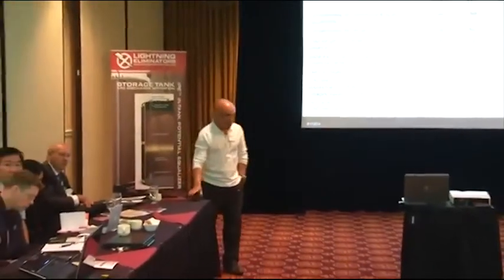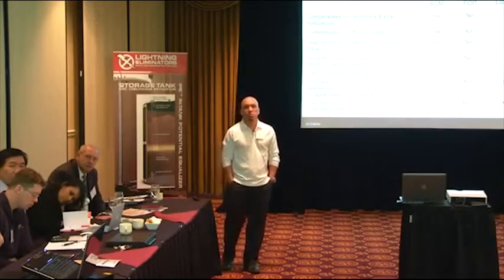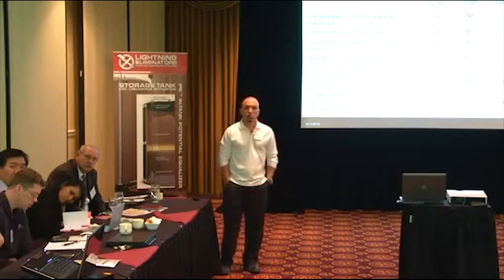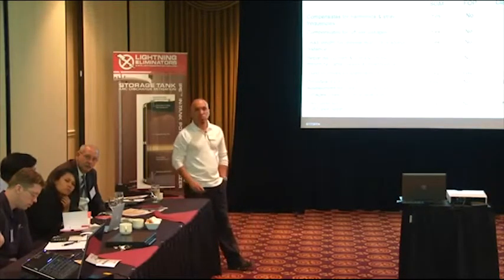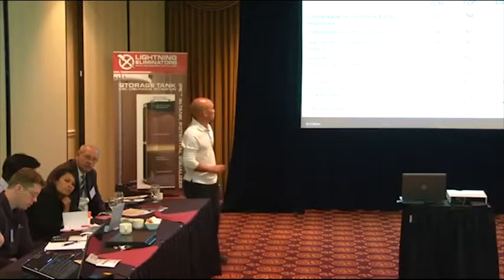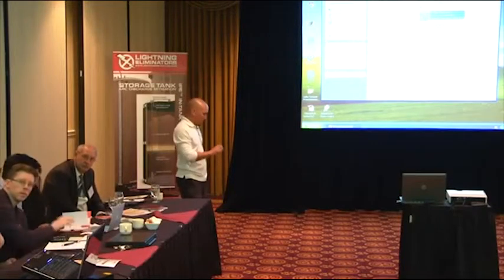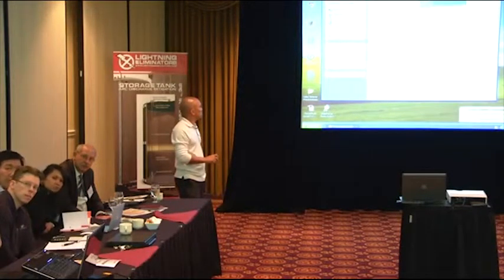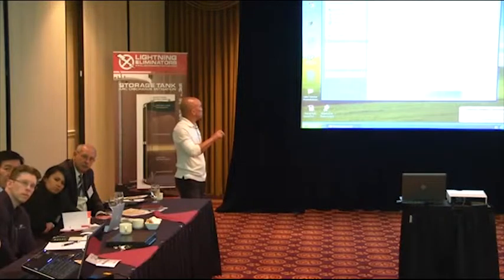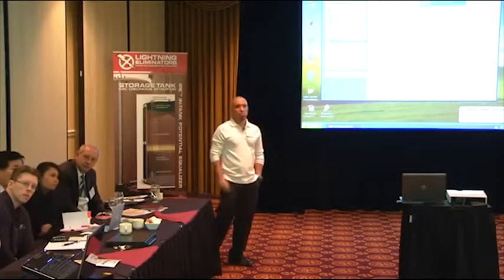Well, as you and I discussed, a lot of times I use this as an entree. We do a lot of paid surveys and go out and visit plants, and customers pay us to come out and take a look at what's going on with their facility. A lot of that's visual inspection. You don't really know what's going on grounding wise. There's a lot buried under the ground. What we're concerned about is what is in the ground, not necessarily what's bonded and above ground, which you can physically see. So a lot of times in doing these surveys, if the plant has any age to it, obviously there could be corrosion and so forth going on in the grounding system. If they're having ongoing problems with lightning and so forth, there could be problems with the grounding system.